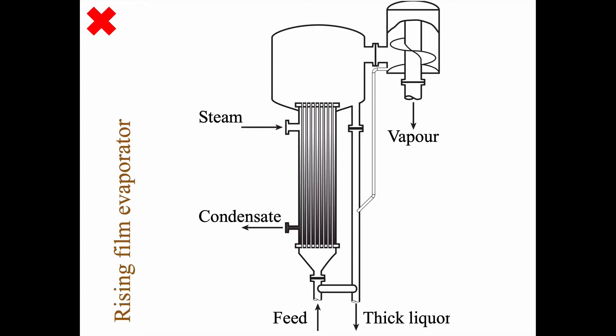Here is a schematic view of the rising film evaporator. The feed comes in at the bottom, steam comes in and exits as condensate, and both the liquid and the created vapor rise up into a dome-like structure and go into a phase separator. Some liquid comes out directly, and some liquid that follows the vapor gets caught and flows back, so you get thick liquor out at the end.